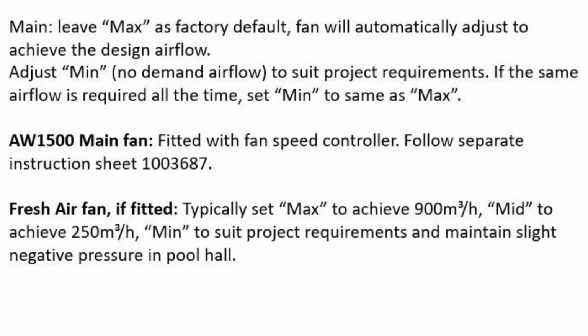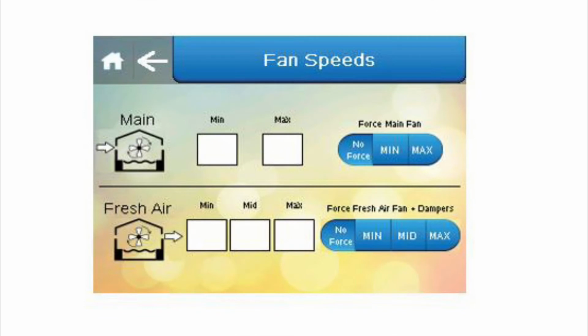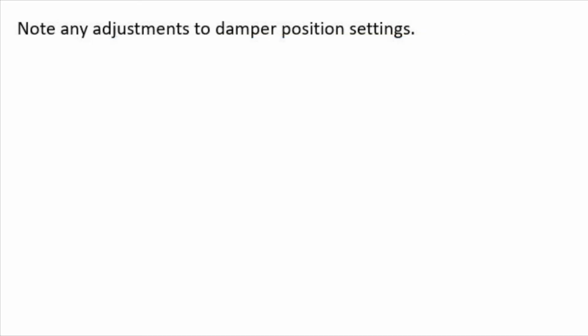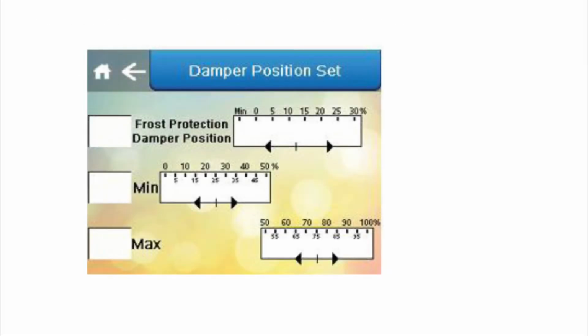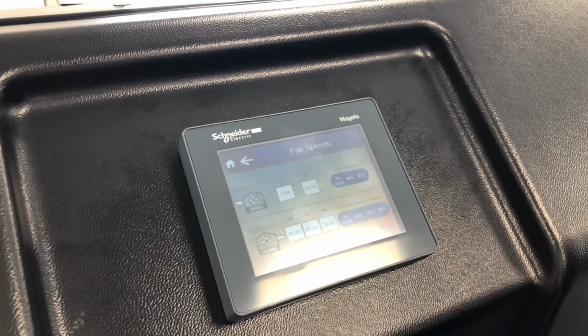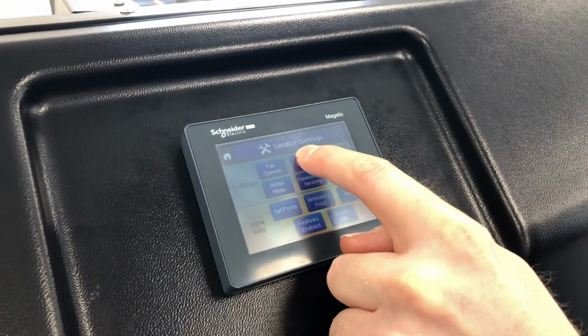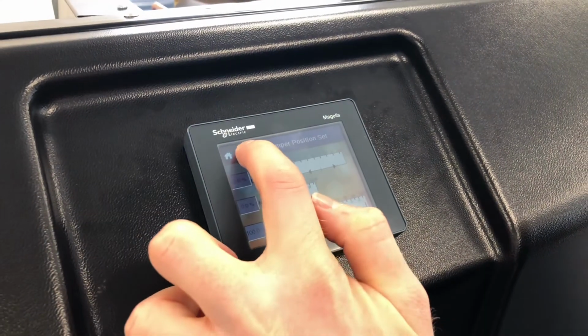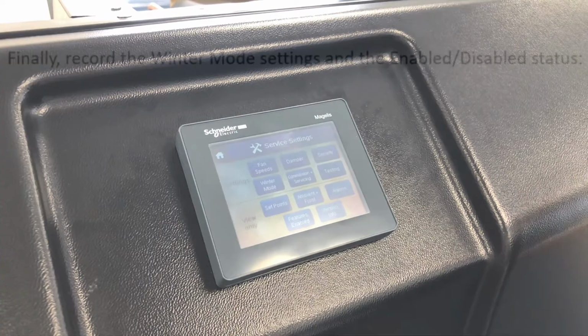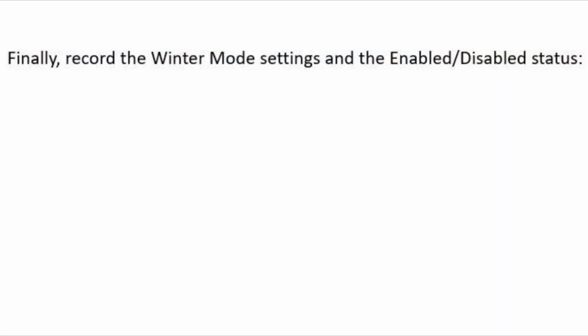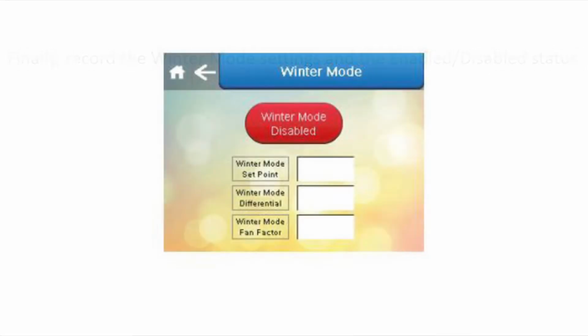As a default, the main fan will adjust to achieve the design airflow of the AHU. To suit the project requirements, you can also adjust the minimum airflow field as necessary. Again, the fresh air fan can be adjusted in the same way to suit the project. Note any adjustment to the damper positioning as a result. These are located in the service settings menu as demonstrated. Finally, record the winter mode settings, also located in the service settings menu.